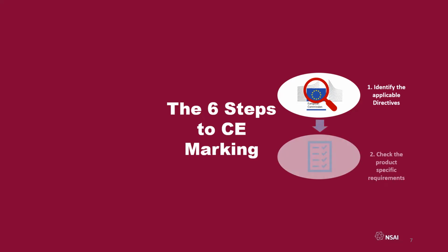The second step, check the product specification. You should then check the exact requirements set out in the regulation and the standards that would demonstrate that your product conforms to the regulations. In most cases, your product will be required to conform to harmonized European standards, which are published in the EU's official journal. If there are no harmonized standards, you will then have to use another standard. You will then need to work down through a hierarchy of standards to find the correct one.